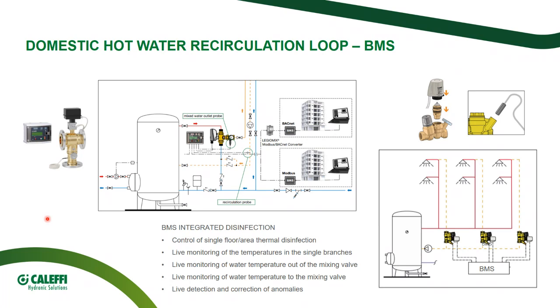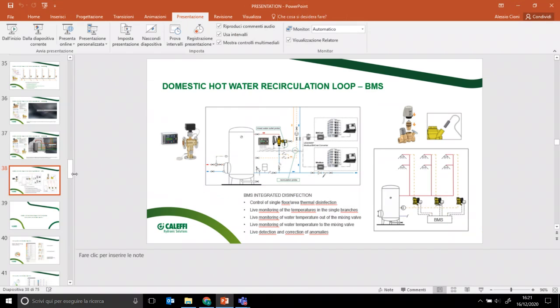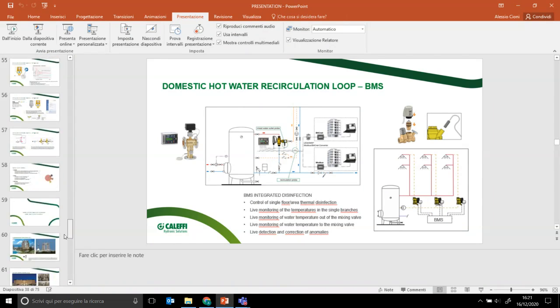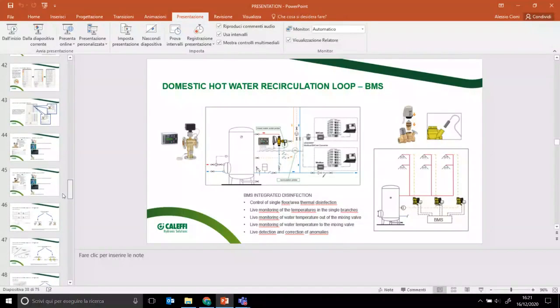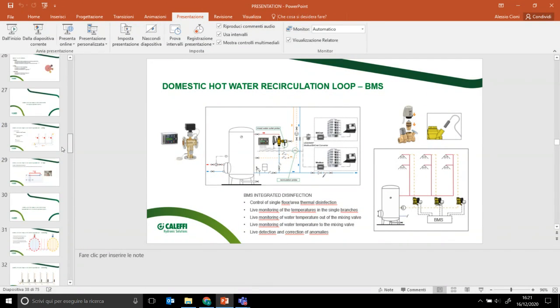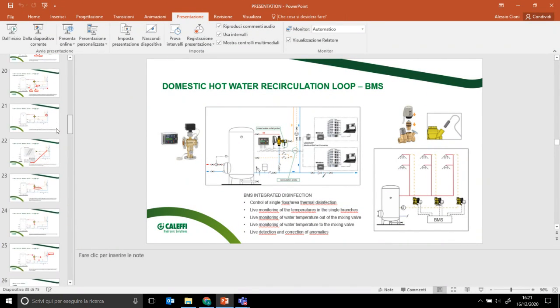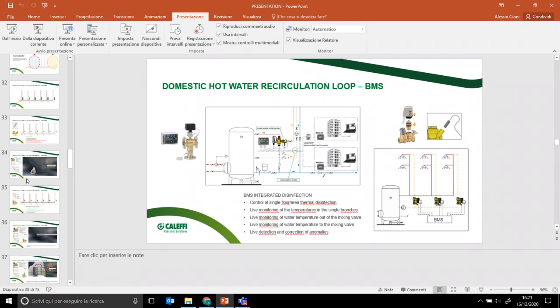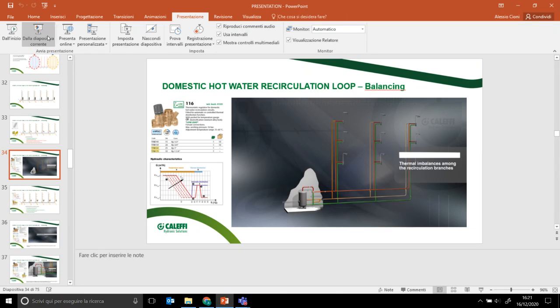No problem. CIBSE Guide G has a procedure explaining how the sizing of a hot water secondary circulation system using thermal balancing valves differs from sizing without this type of valve. Does Caleffi provide the necessary data for this sizing procedure? Of course, I think it is enough to take a look at the hydraulic characteristic chart. I just reported it for your information, so it's quite small, but it is enough to understand.